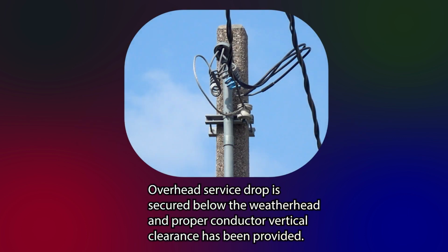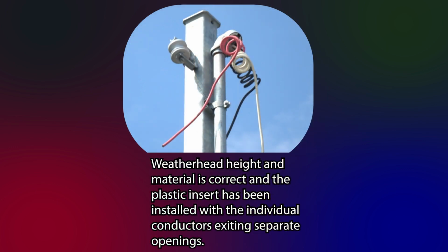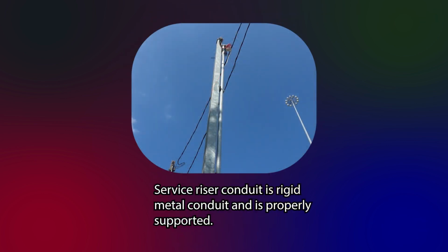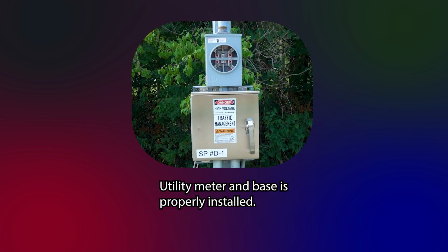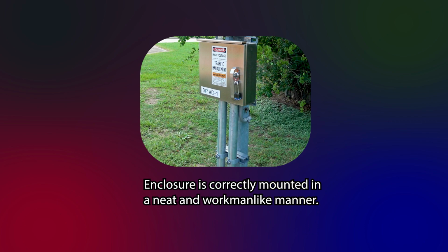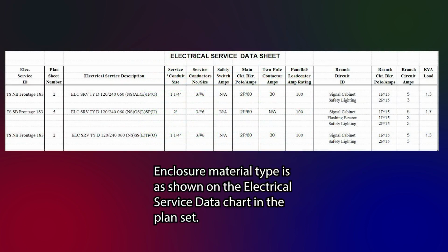Overhead service drop is secured below the weatherhead, and proper conductor vertical clearance has been provided. Weatherhead height and material is correct, and the plastic insert has been installed with the individual conductors exiting separate openings. Service riser conduit is rigid metal conduit and is properly supported. Utility meter and base is properly installed. Enclosure is correctly mounted in a neat and workmanlike manner. Enclosure material type is as shown on the electrical service data chart in the plan set.